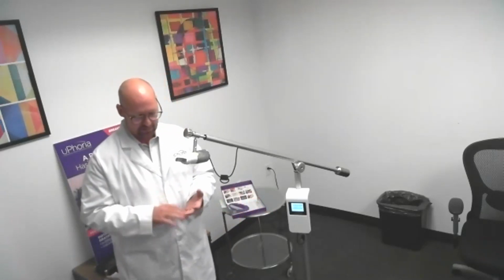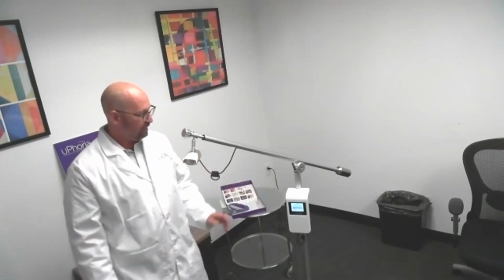As long as you're having this nice light contact and the foam pad is touching the patient's teeth, it will work. And then it will ensure that you do not have a foam pad that has spots that are dry. So the three most important things are case selection, or shade selection; number two, making sure you have a fully saturated foam pad; and number three, like I was saying, don't apply excessive force.